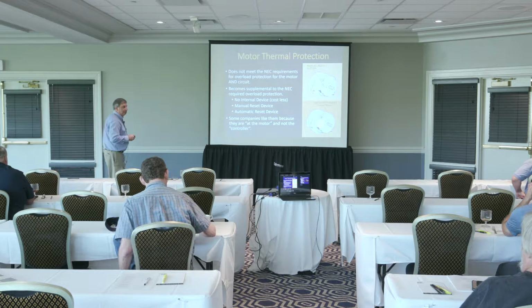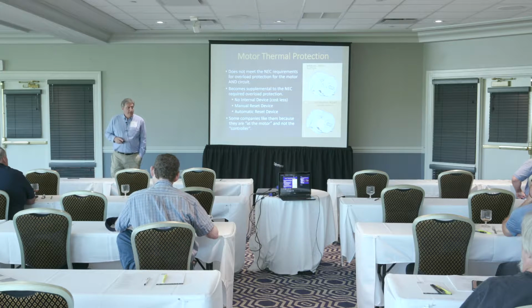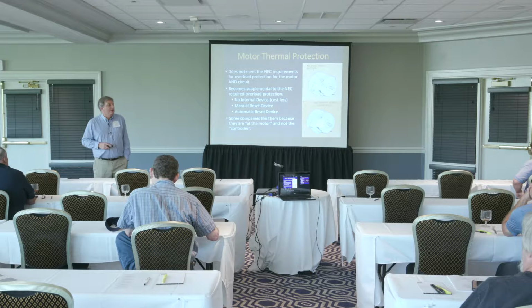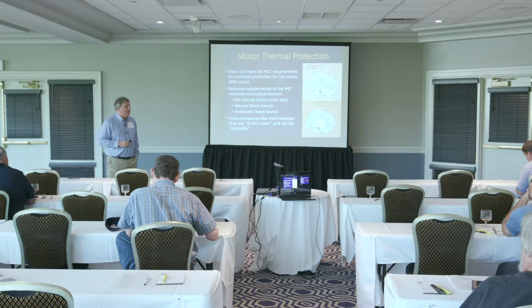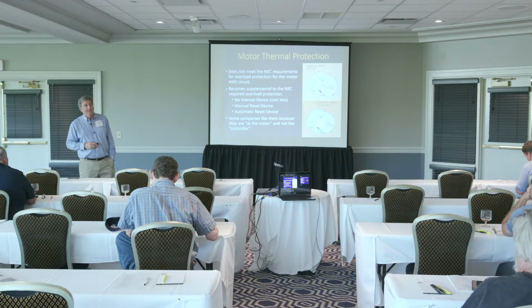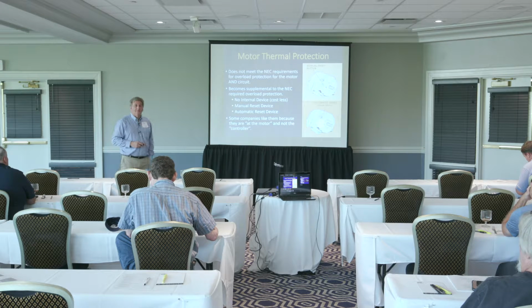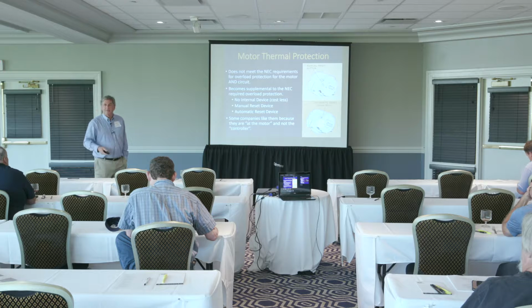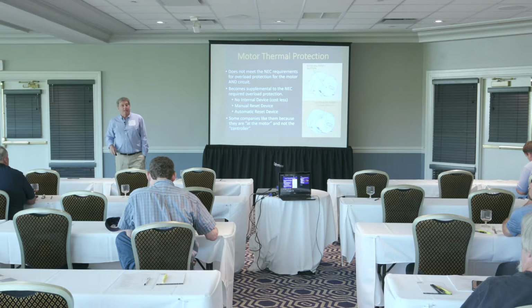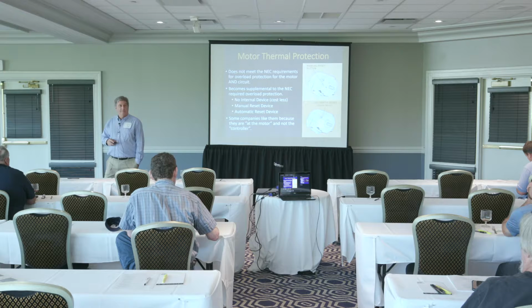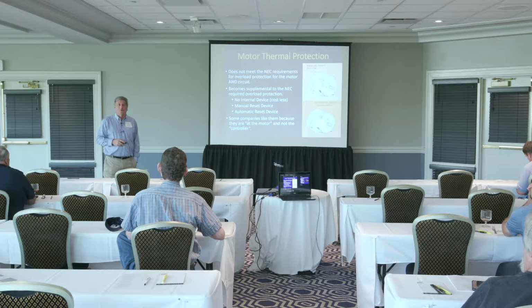I always tell people, depends on who's asking the question, okay, Mr. Stark, what would you have done differently in terms of the company protecting its workers if you knew that motor could come on automatically? Well, one option is to make sure only qualified employees can get near that motor by barricading it behind a fence or in a room where the access is controlled, like NFPA 70E says you can do. The other part of the question that I just mentioned, about half of those people getting hurt are unqualified employees. How did an unqualified employee get so close to that piece of equipment?